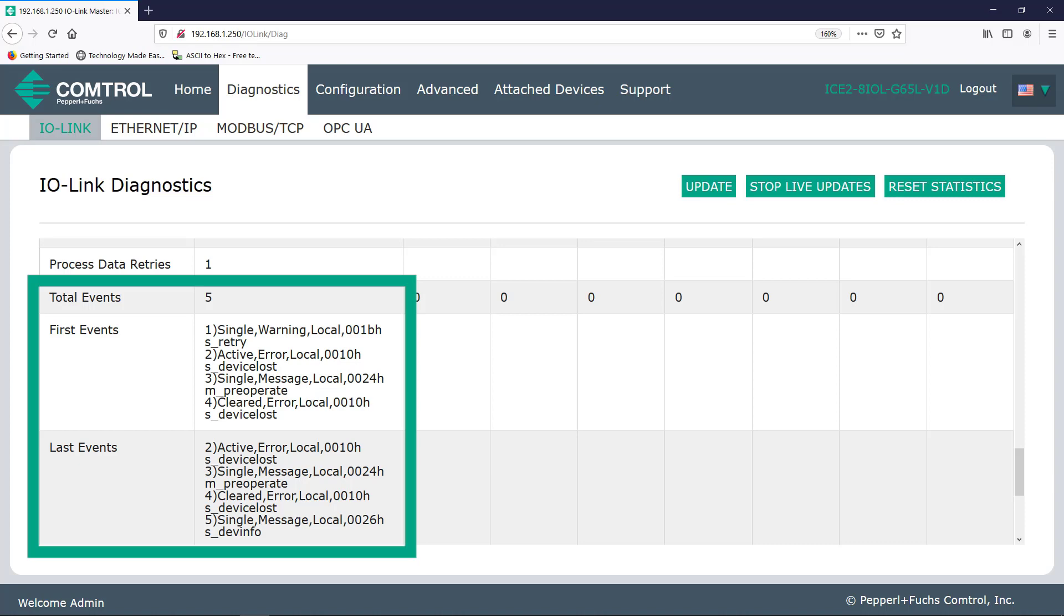Now, when speaking about IO-Link and RFID, you'll primarily be concerned with process data, which is cyclic data and service data or ISDU. And this is true for most sensors. Now, some manufacturers might provide more useful information here in the event section, but generally you might not need to pay much attention to these. These events may cover things that are less severe than something like a whole device failure.